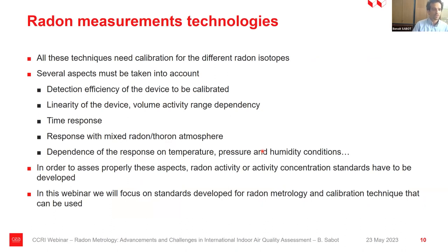Some radon detector can give a response of activity concentration quite slowly or at the opposite, very fast. Also how they act when you have a mix of radon and thoron atmosphere. And of course the response depending on temperature, pressure, humidity condition and so on, because you are measuring in the environment and you are not able to always know all these parameters and how they will change over the days.